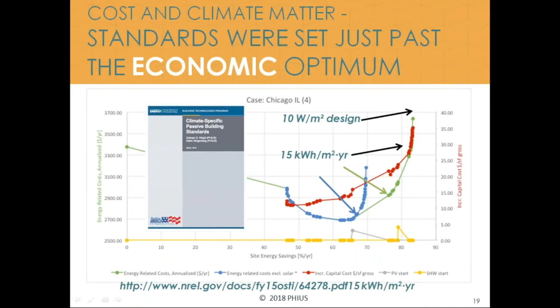We also looked at what would happen using the European design guidelines—15 kilowatt-hours per square meter per year for heating demand, or 10 watts per square meter. Both targets would have pushed us significantly back up into diminishing returns, to a point where we were even more expensive than the baseline. The two options aren't equal either: meeting 10 watts per square meter pushes you even further up into diminishing returns in this climate, because it's almost impossible to achieve there.